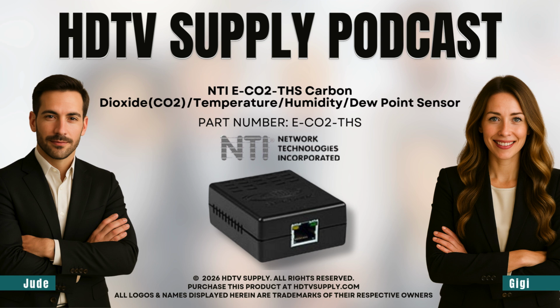Okay, think of it like this. Humidity is just the amount of water vapor in the air. High humidity is bad, we know that. But dew point is the exact temperature where that invisible vapor stops being vapor and becomes liquid water. A puddle on your motherboard, which is an instant short circuit, game over. Exactly. If you're only watching relative humidity, you could totally miss the danger zone when the temperature fluctuates. This sensor calculates it so you know the exact moment condensation becomes a physical threat. That's a huge distinction.